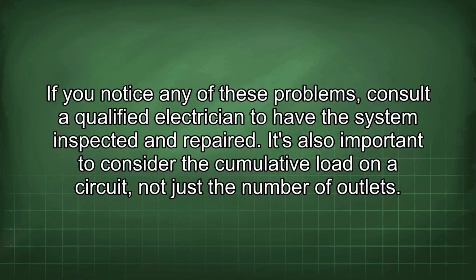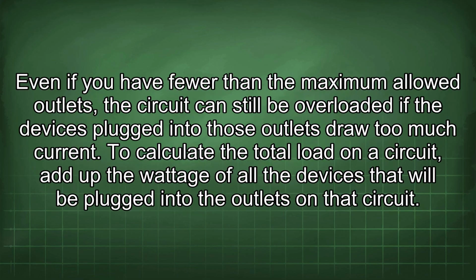It's also important to consider the cumulative load on a circuit, not just the number of outlets. Even if you have fewer than the maximum allowed outlets, the circuit can still be overloaded if the devices plugged into those outlets draw too much current. To calculate the total load on a circuit, add up the wattage of all the devices that will be plugged into the outlets on that circuit.